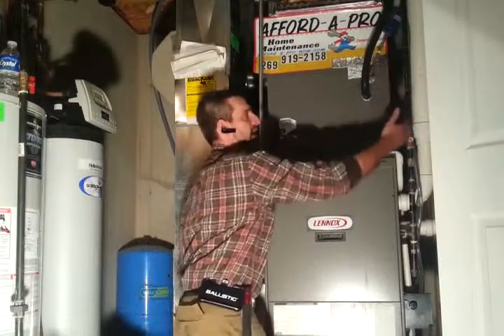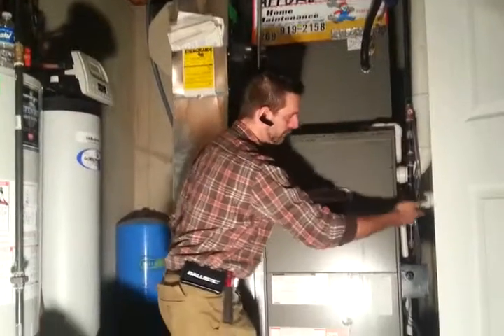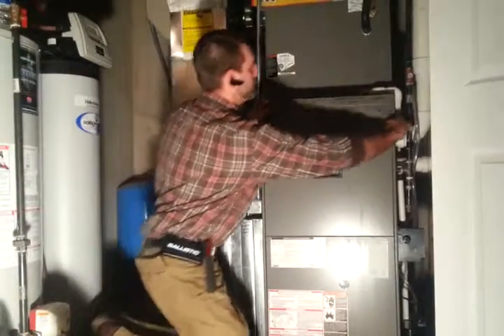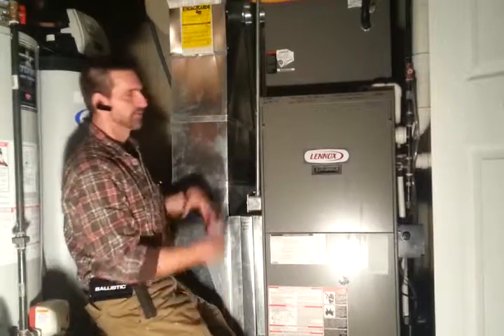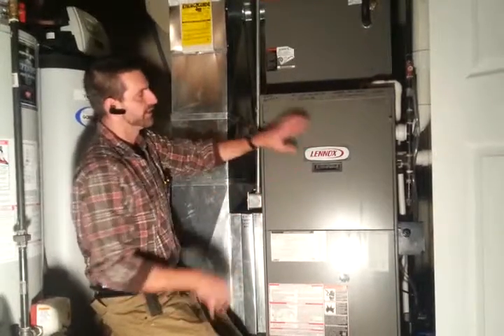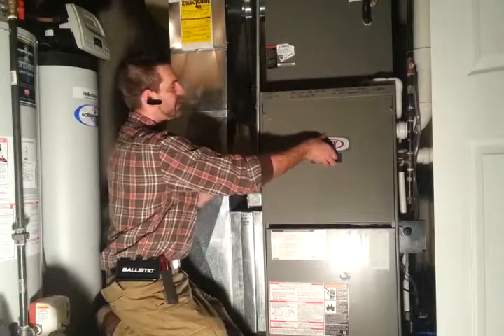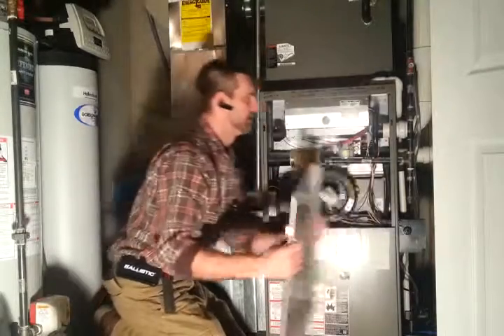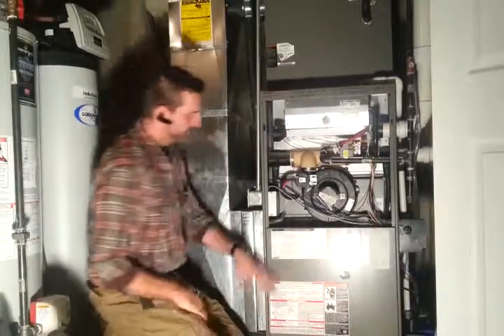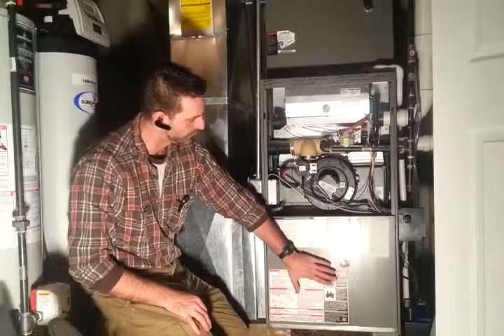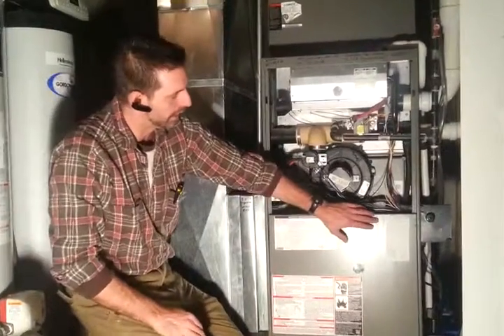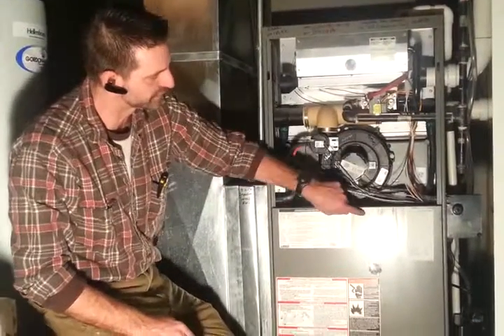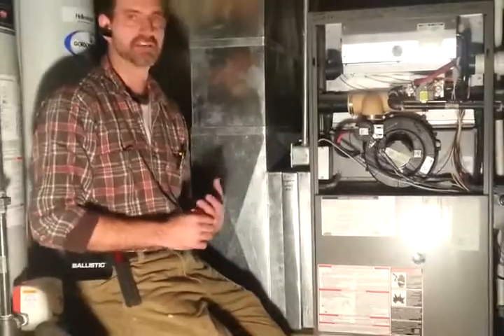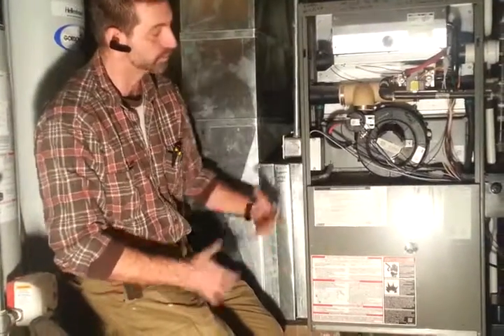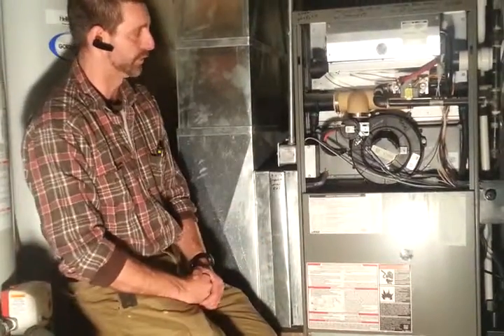Okay, here's my gas line. You can see the gas shut off. It comes down and into my furnace. So let's take this cover off. This cover, on any furnace, you can get into without any problems. There's no safety switches or anything behind it. Unlike this cover, once this cover is opened up, you're going to kill power because there's always a safety switch. I always take that safety switch off and have done so on this one, so I can open this up without killing power to it.